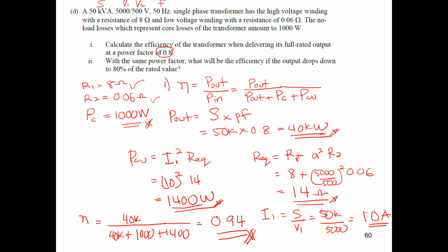Then you find I1. Since the question doesn't give I1 directly, I1 equals S over V1, which is 10 amps. Putting in all the values gives P copper as 1400 watt. Then you calculate the efficiency: P out is 40K, divided by 40K plus 1000 (core loss) plus 1400 (copper loss), giving 0.94. There is no unit for efficiency, so it's just 0.94.